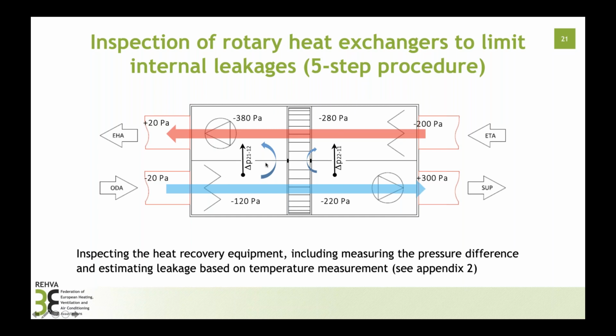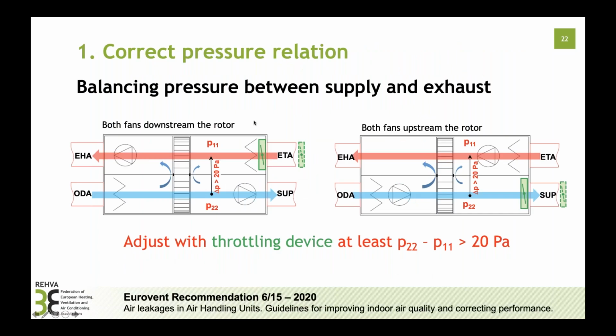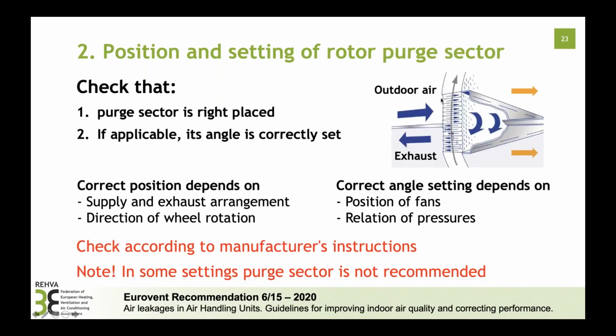Basically, on both sides of the rotor, it is important that the pressure direction is from the supply side to the return air side. There are negative pressure values because we are on the suction side of the fans on both sides, but it means that the negative pressure values need to be higher on the return air side. And that's a recommendation on how to correct these pressure differences if they are not correct. It is recommended to have 20 pascals minimum. And it is important that the purge sector of a rotor is correctly functioning, because this will assure that particulate matter will not be transferred.